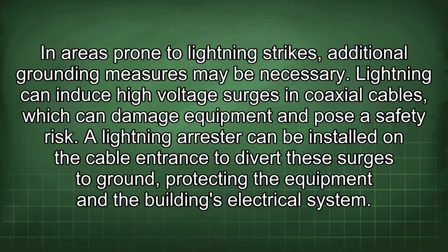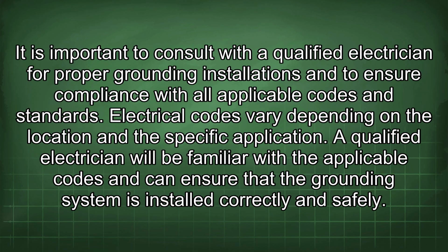In areas prone to lightning strikes, additional grounding measures may be necessary. Lightning can induce high-voltage surges in coaxial cables, which can damage equipment and pose a safety risk. A lightning arrestor can be installed on the cable entrance to divert these surges to ground, protecting the equipment and the building's electrical system. It is important to consult with a qualified electrician for proper grounding installations and to ensure compliance with all applicable codes and standards.